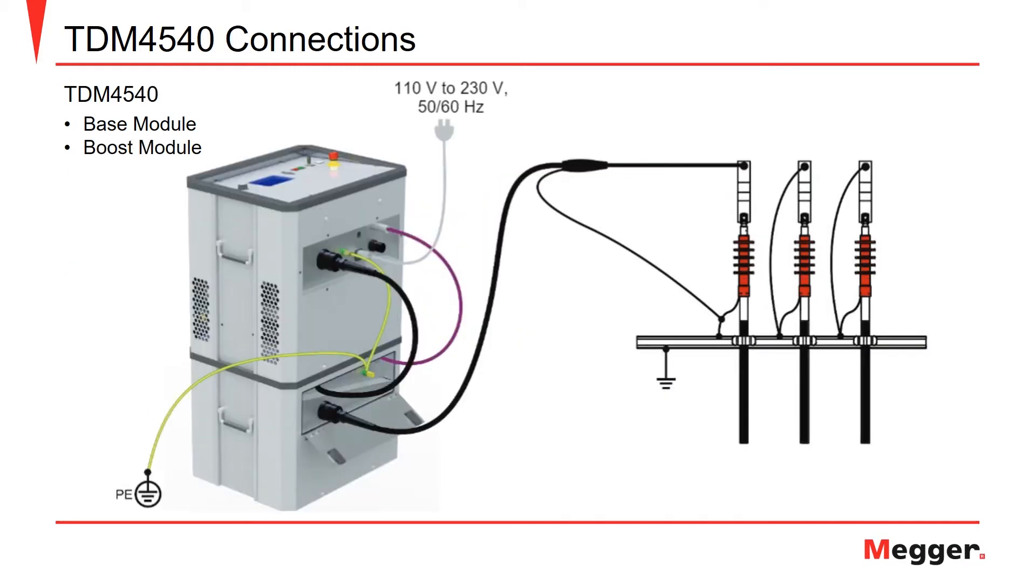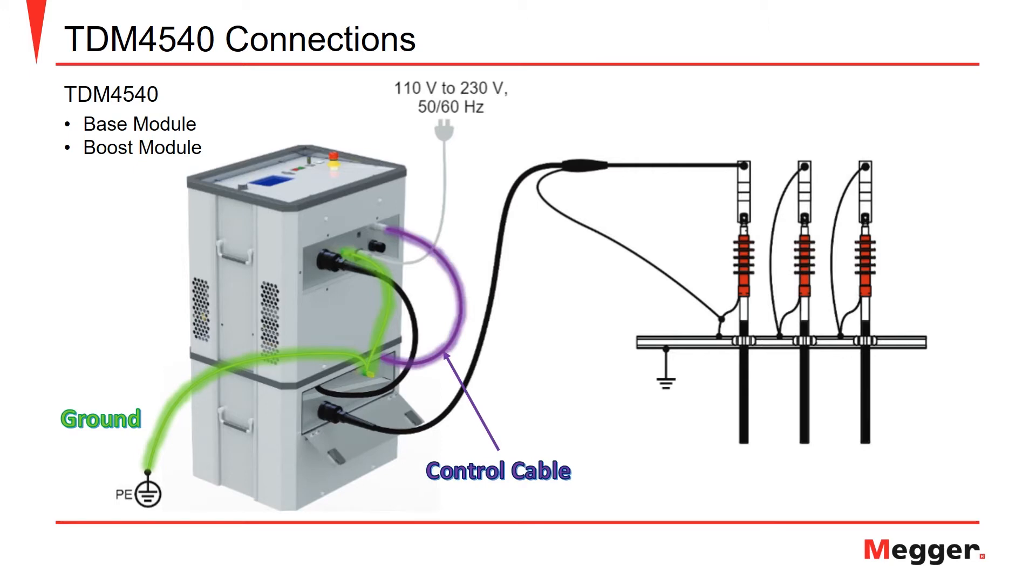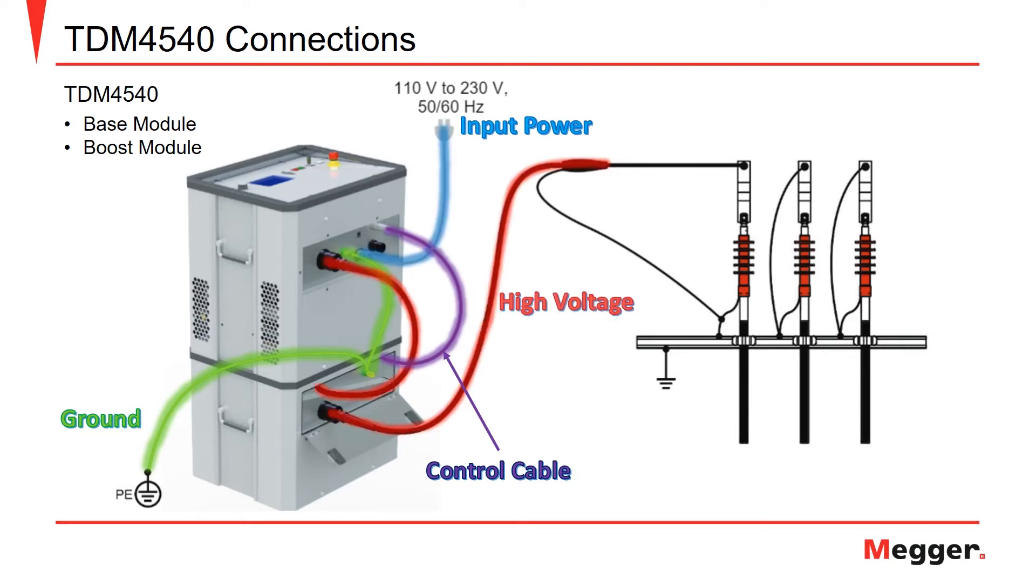In the next example, we can see the typical connections required to perform a VLF or tan-delta test using the TDM4540, which is comprised of both the base and boost module, as well as the necessary connections. The connections for the TDM4540 include the ground connection from the base to the booster module and to the station ground, the control cable interconnecting the base and boost module, the input power to the unit, and the high-voltage connection that interconnects the base and boost module, as well as going from the boost module to the cable under test.